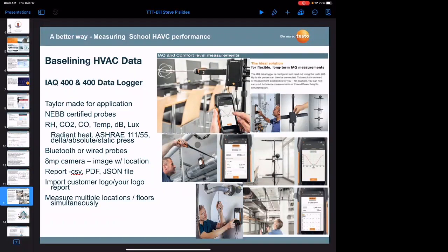One of the easiest ones, and it's hard to see here, but you see this square grid here and a number of dots. Well, that's the ASHRAE 111 protocol. That is a really simple thing whereby the unit will say, okay, so you want to employ ASHRAE 111. How big in length and height is the duct that you're going to measure? Is it square? Is it rectangular? Is it oval? Or is it round? And you pick one of those 4.